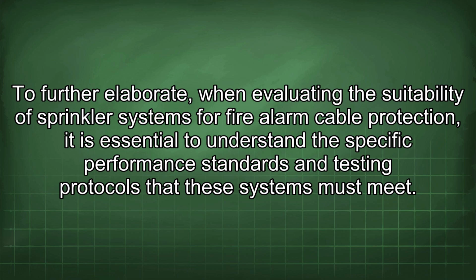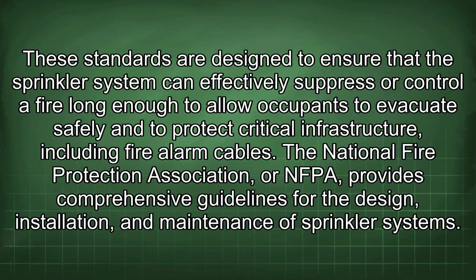To further elaborate, when evaluating the suitability of sprinkler systems for fire alarm cable protection, it is essential to understand the specific performance standards and testing protocols that these systems must meet. These standards are designed to ensure that the sprinkler system can effectively suppress or control a fire long enough to allow occupants to evacuate safely and to protect critical infrastructure, including fire alarm cables.